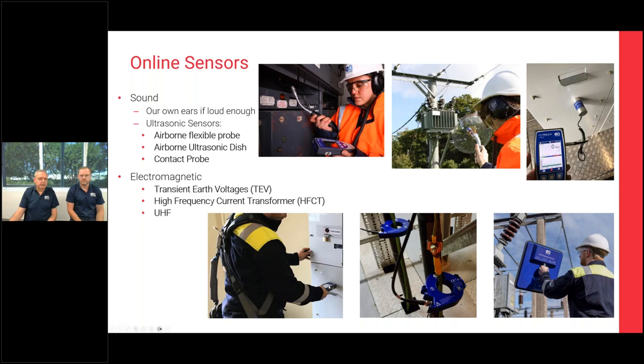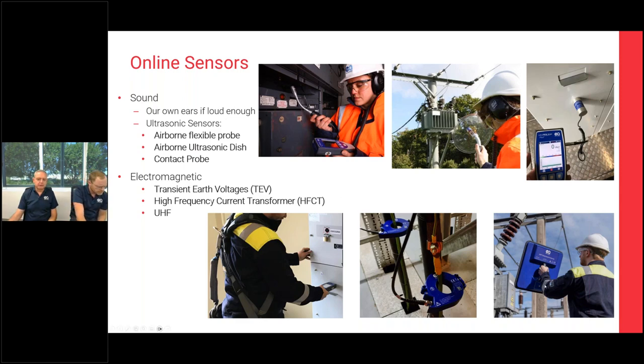For electromagnetic techniques, we use Transient Earth Voltage (TEV), which is a capacitive plate on the end of the ultrasonic instrument. We can use HFCTs which go around earth braids, particularly on cables, and UHF techniques for distance work — especially in high-voltage switchyards where localization using UHF is preferable. We have a UHF directional antenna shown in the bottom right picture. All of these techniques will give us the PRPD patterns we're discussing today.